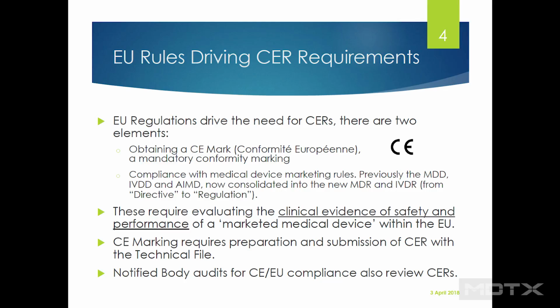Okay, so CE marking, for those of you who are not as familiar with that process, requires submission of the CER with the technical file. The technical file is an entire topic. We could talk for hours about it, but the CER is a component of that, so it's a piece you want to think about when you're obtaining your CE mark.